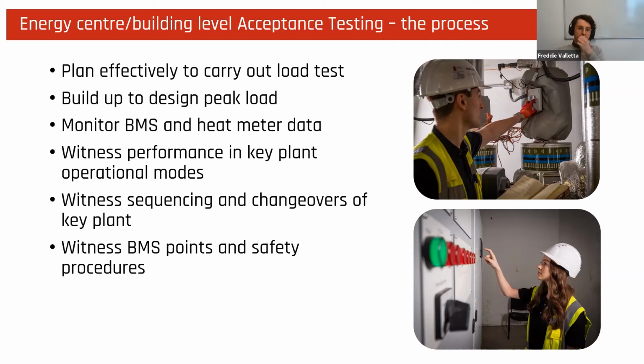Load is introduced gradually onto the system, building up to that design peak load. In particular, it will focus on key plant operation modes, i.e. additional boilers or pumps coming on or offline, changeover of heat generation equipment once the thermal store is depleted, for example. This particular focus on sequencing and changeovers ensures that heat delivery is not compromised in these periods of changing load. Return temperatures actually remain low as per design, and your pump differential pressure is maintained across the network.